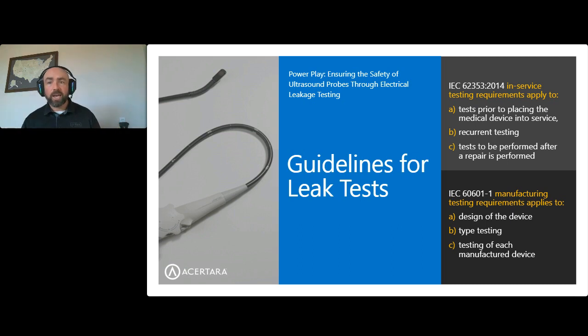So you do have good agreement on how the testing should be done, even if specific limits for an individual probe can be different. There are absolute limits over which they cannot go and still be used, regardless of what the particular OEM says about their device. Those tend to be at 175 microamps.